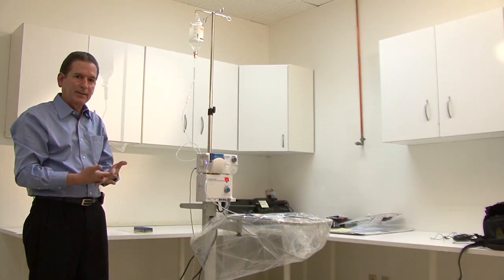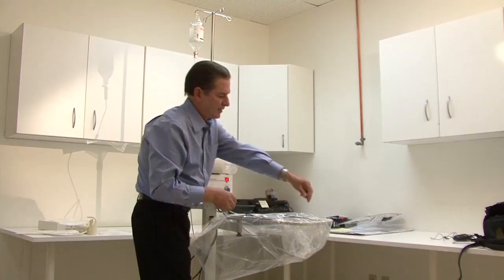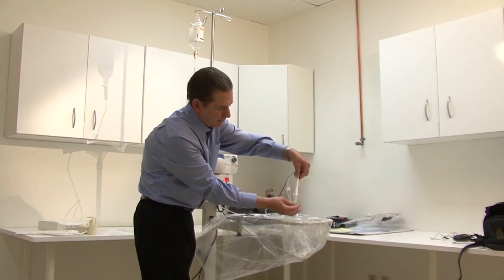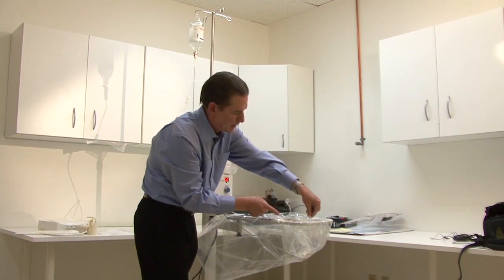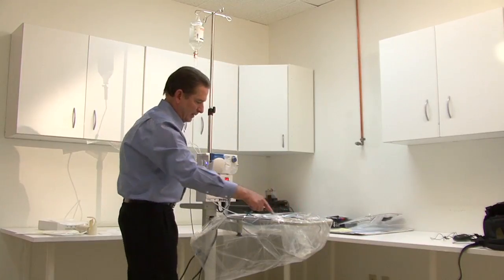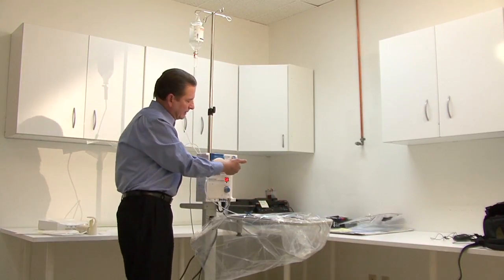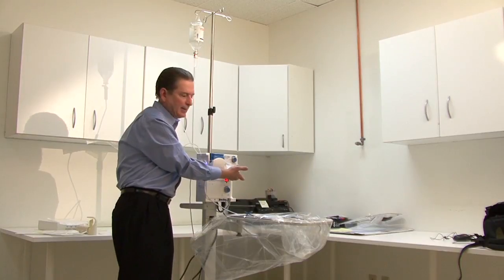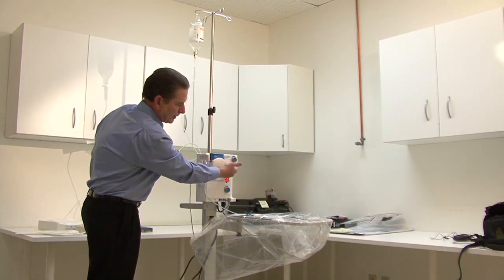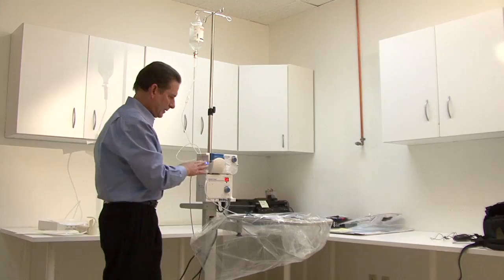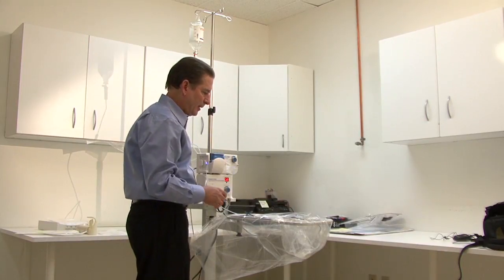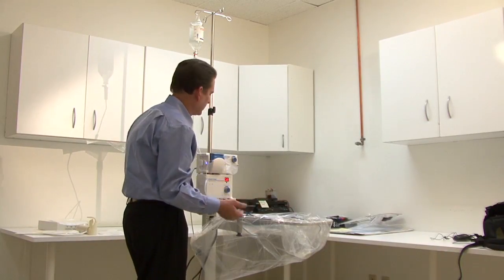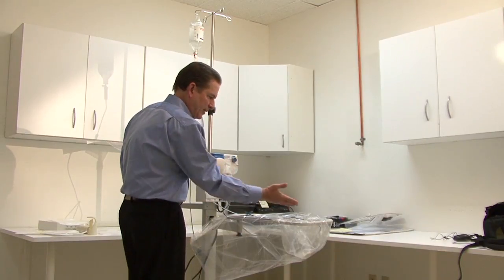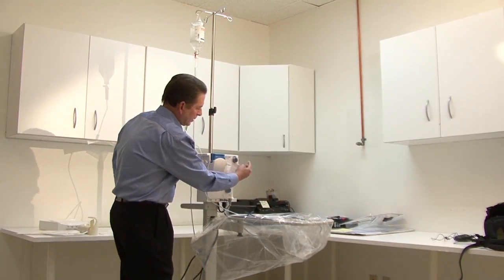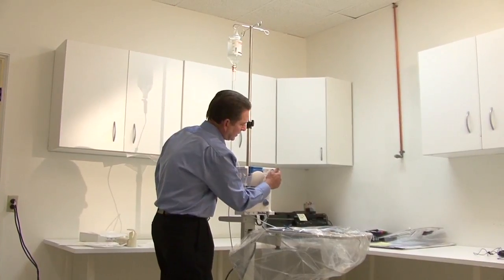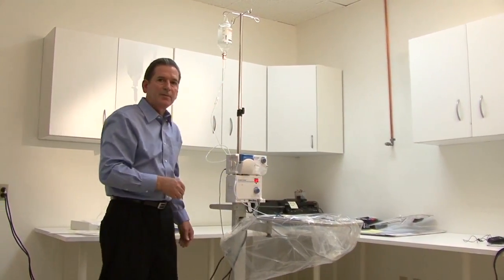And all we do is just let the system run. What will happen is the irrigation will continue to flow into the cap. When the tip's submersed, the pump will aspirate through the aspiration line and we'll start seeing it drip into the collection bag. So when we see it start dripping in the collection bag, we can just do a quick visual check. At that point, we shouldn't see any bubbles in the line. If we do, we can just let the prime run longer. But once it's dripping, we don't see any bubbles in the line. We can go ahead and go to surgical mode, flow 3, and we're all set for surgery.